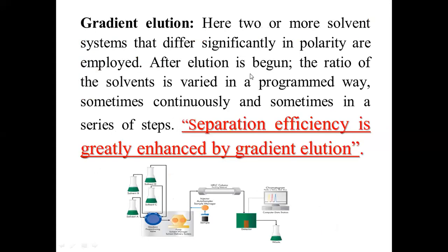Gradient elution means, assume 10 solutes are present. You elute two solutes by using one mobile phase, you elute three other solutes by using another mobile phase, and you elute some other solutes by using some other solvents as a mobile phase. So two or more solvents are used, and these solvents are selected based on their polarity, because the polarity index is very, very important in deciding a successful elution process. Once the elution has begun, the ratio of the solvents is varied by programming.